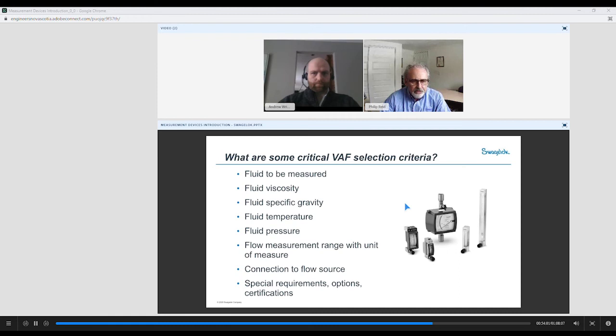So with that, we have a few things that you need to know when you're going to be selecting a flow meter. And a flow meter is a device used, again, to measure the fluid. So you want to know what that fluid is that's being measured. Is it a gas? Is it a liquid? Is the fluid viscosity available? Is the fluid specific gravity? And again, if you're working with water and air, you're fine. You can buy an off-the-shelf flow meter. Otherwise, the calibration will be different. The temperature you'll be operating at, the pressure, the measurement range and the units.